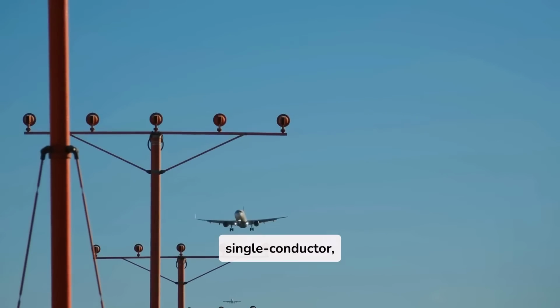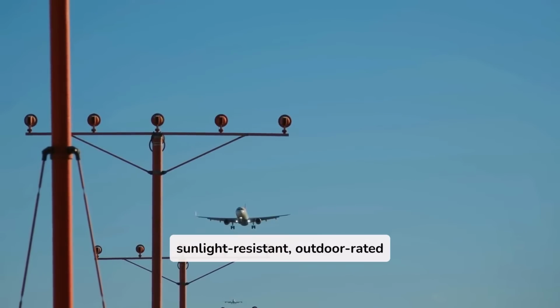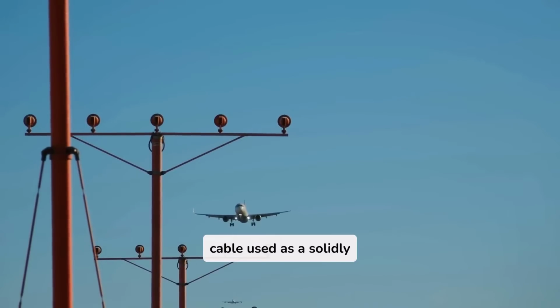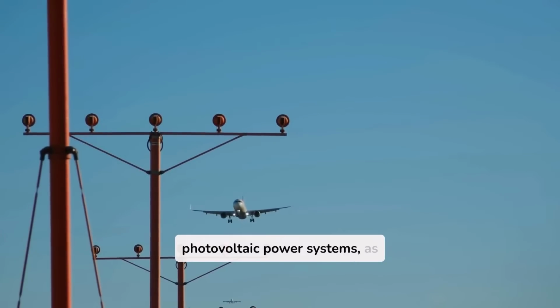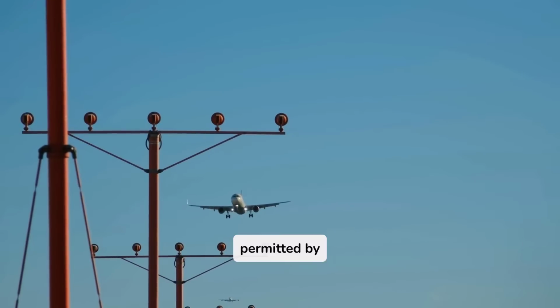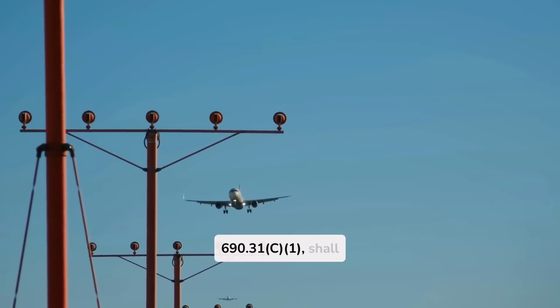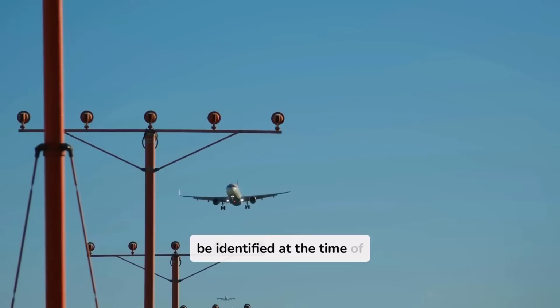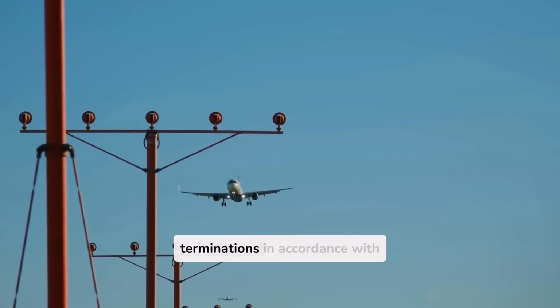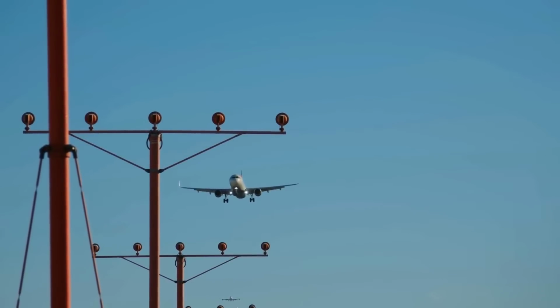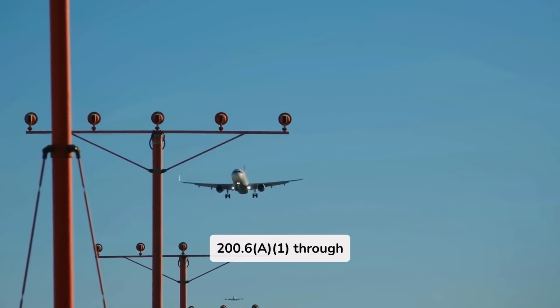5. A single conductor, sunlight-resistant, outdoor-rated cable used as a solidly grounded conductor in photovoltaic power systems, as permitted by 690.31(C)(1), shall be identified at the time of installation by markings at terminations in accordance with 200.6(A)(1) through (A)(4).